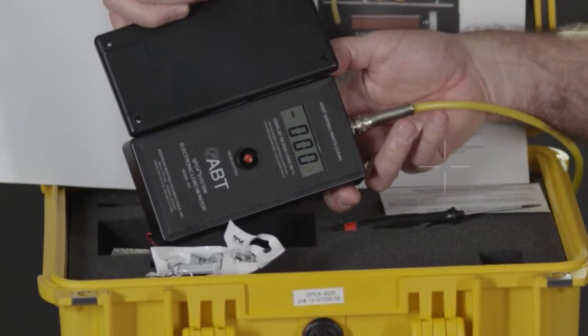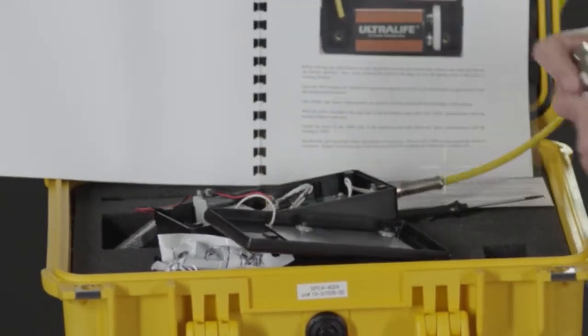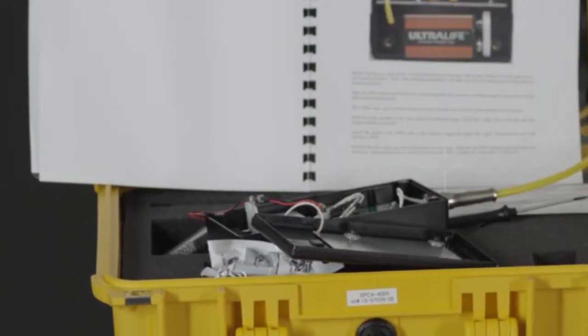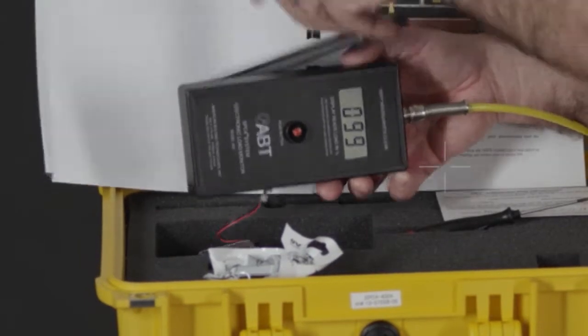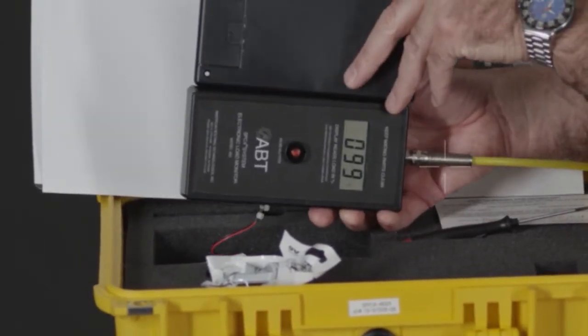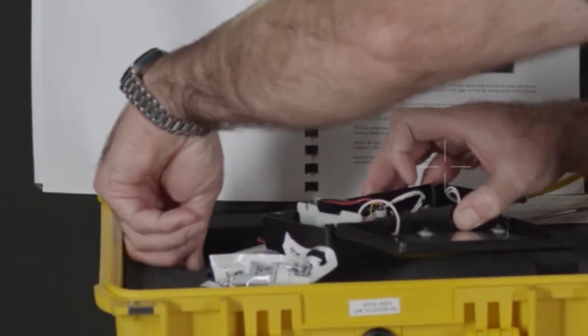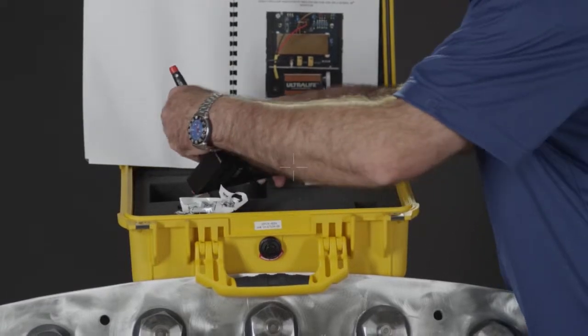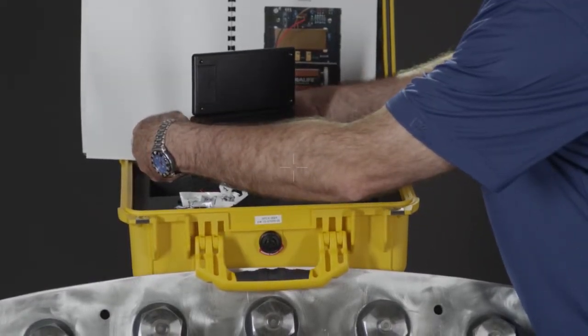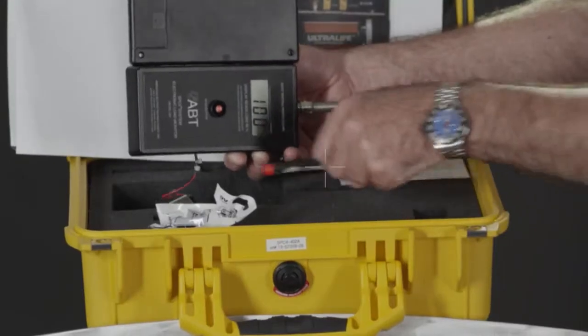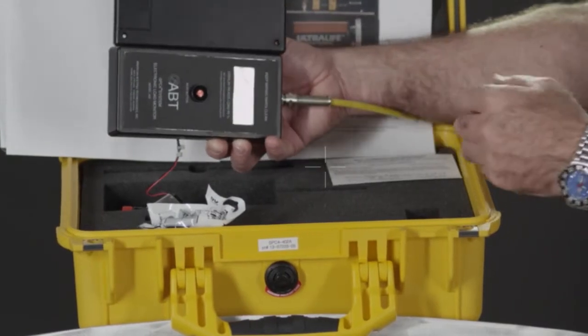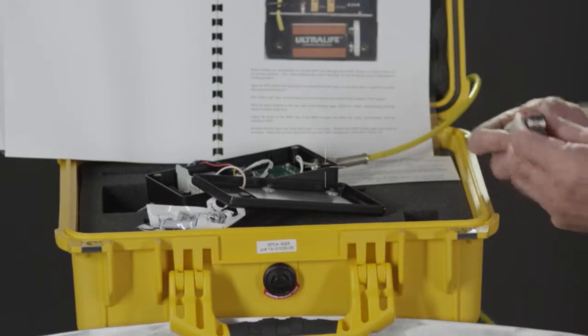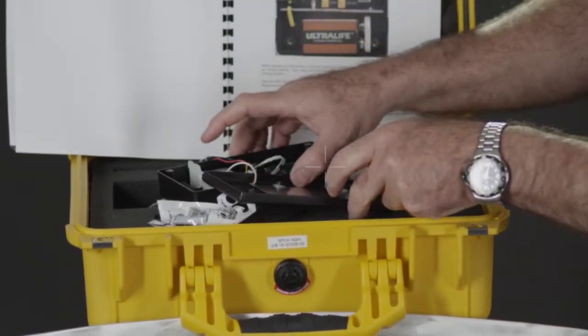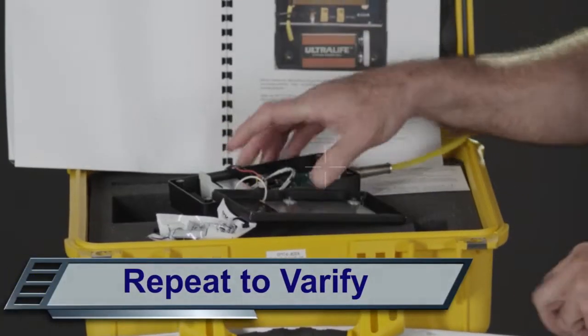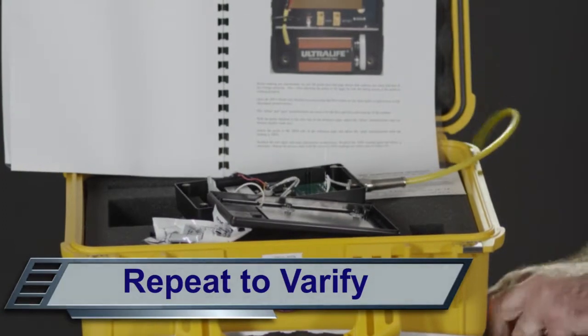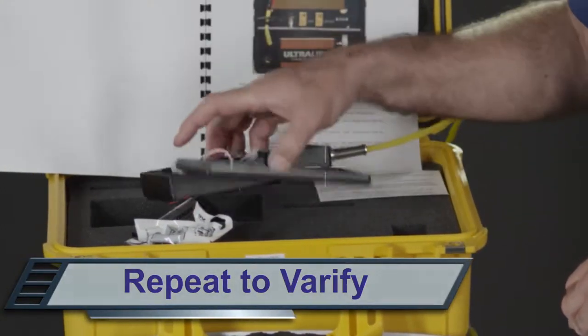Once it reads 0, you take your meter and put it to the 100 side and make sure that you're reading 100. And if you aren't reading 100, then you adjust the gain till it reads 100. So now you've adjusted the 100. You verify the 0 one more time. There's 0, and I always like doing that a couple of times just to verify that it is indeed reading 0 and 100 multiple times.